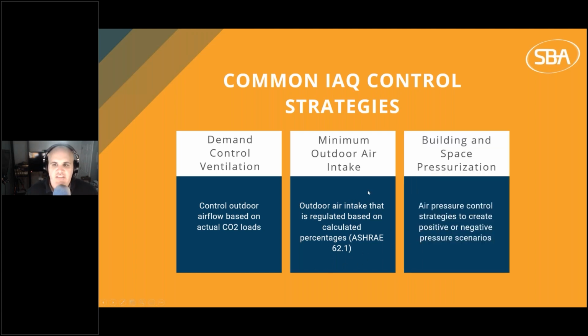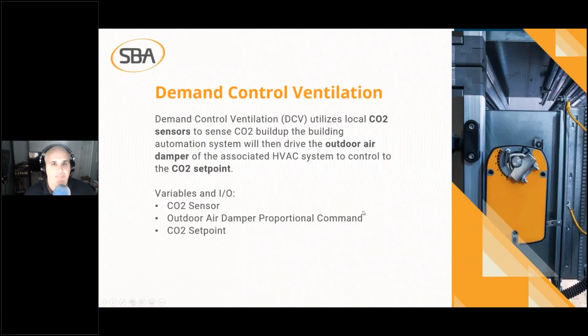And then building space and pressurization. These are strategies to control positive and negative pressure within spaces, usually done through volume changes on the main air handlers, sometimes done at boxes if you have dedicated supply and exhaust boxes in each space. So let's go through demand control ventilation, what it's going to do, and I've boldened on some of these slides the inputs and outputs and set points.